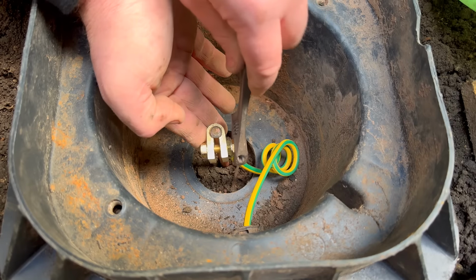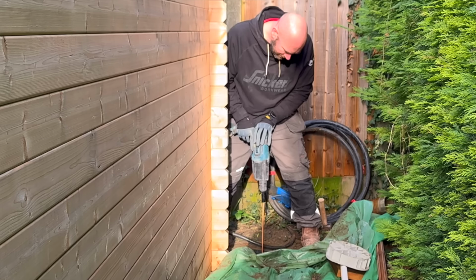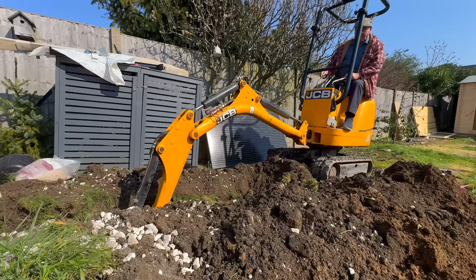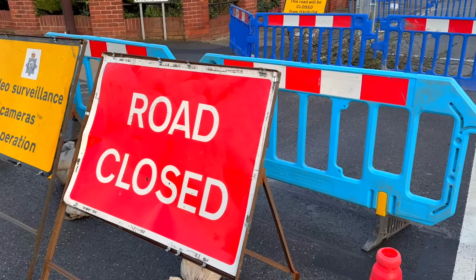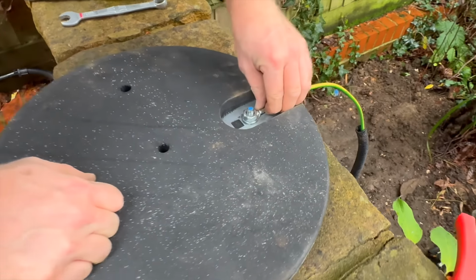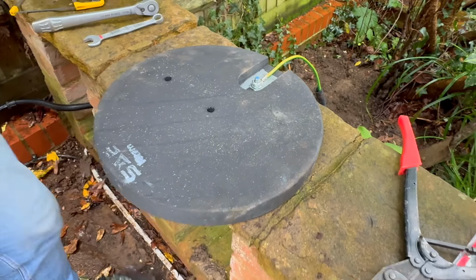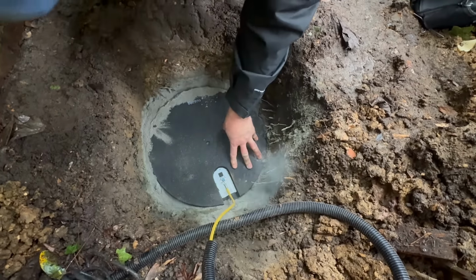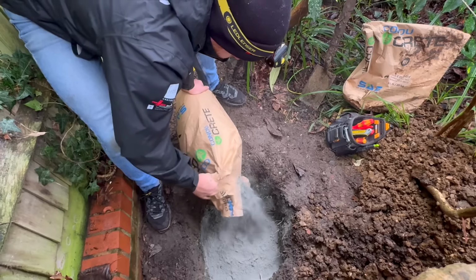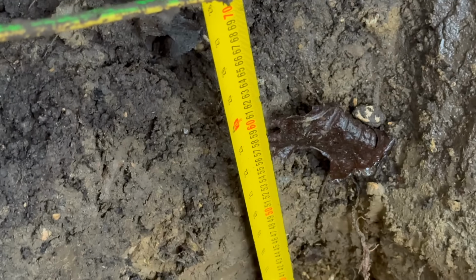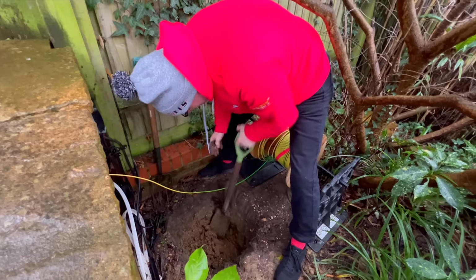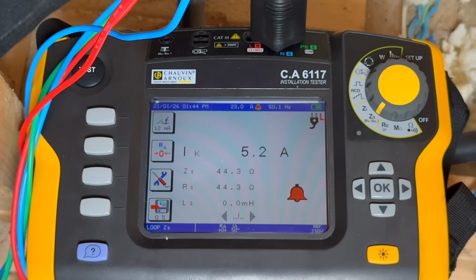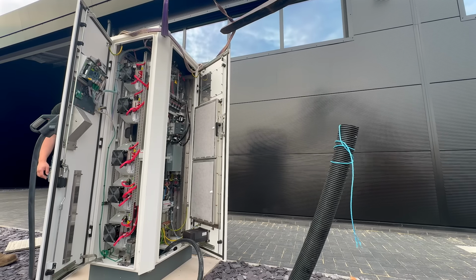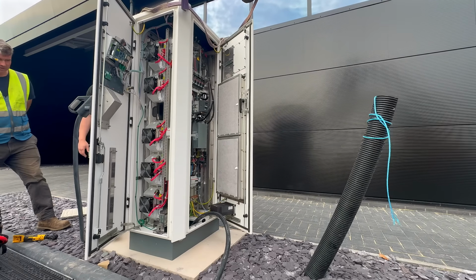The earth electrode helps control touch voltage if something goes wrong, but installing an earth electrode is not risk-free. Driving rods into the ground can bring its own hazards. Underground services, gas, water, telecoms, existing cables, which is why alternative earthing solutions exist. One example is a conductive earth disc system. These provide a large surface area in contact with the soil without the need to drive a rod deep into the ground. They can be installed closer to the surface, reduce the risk of striking buried services, and often achieve very low resistance values. They are particularly useful where ground conditions or site constraints make traditional electrodes impractical.